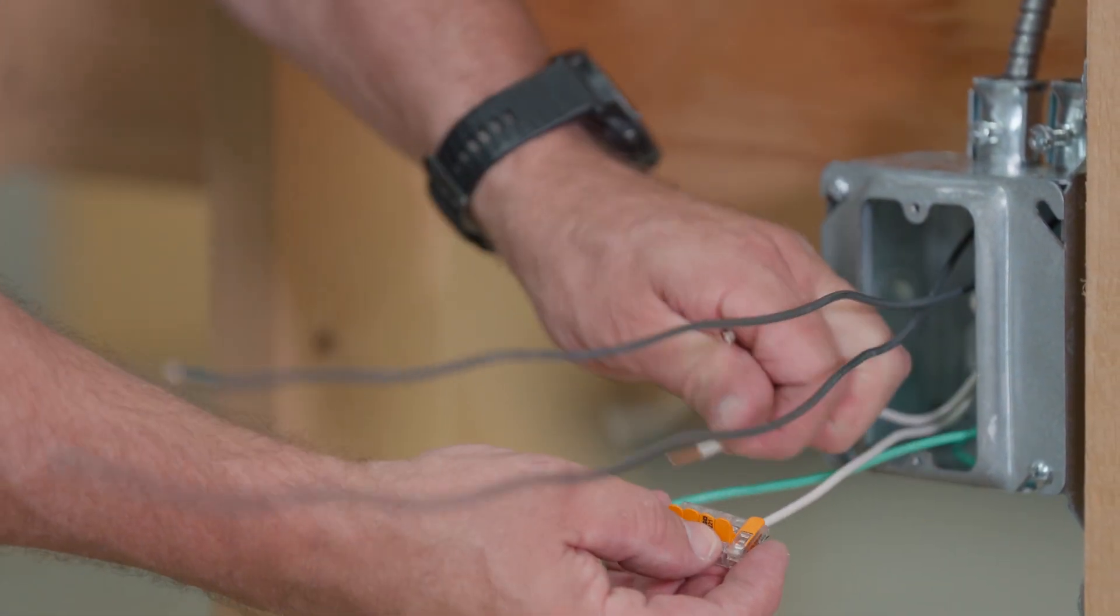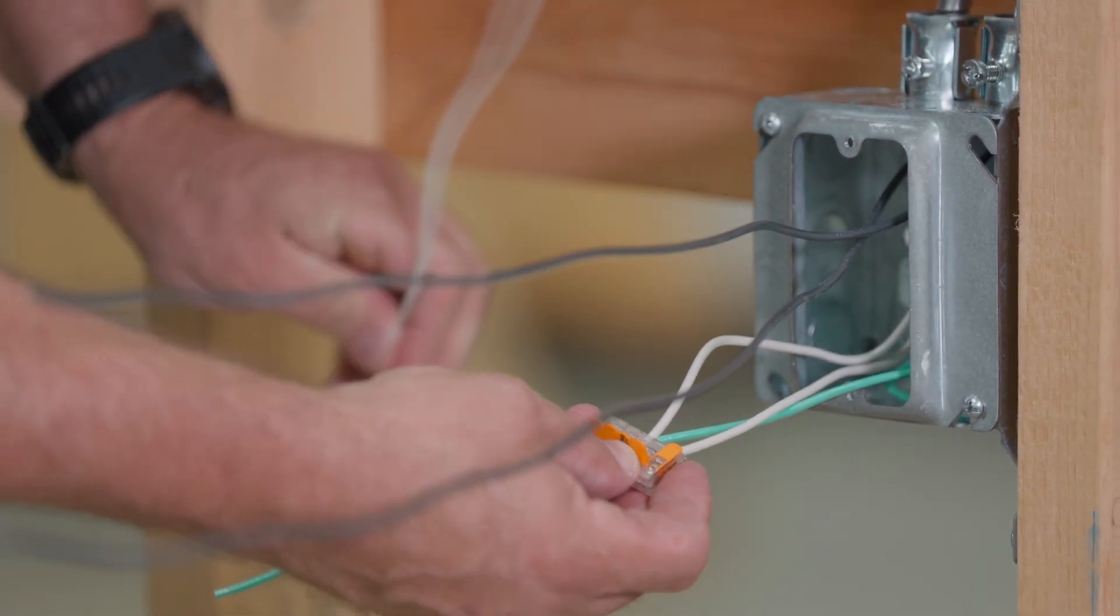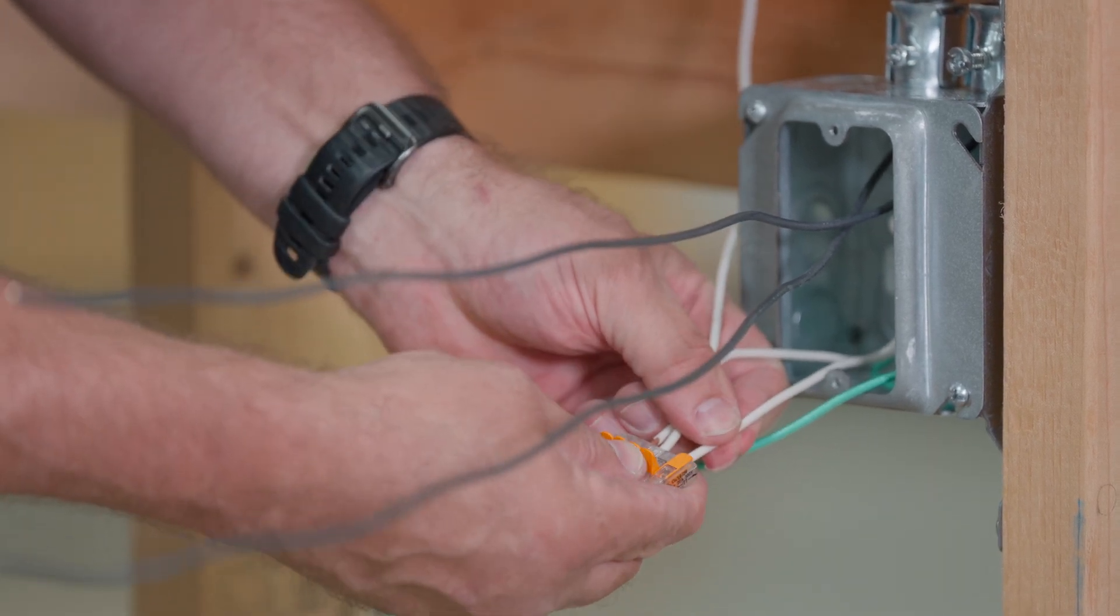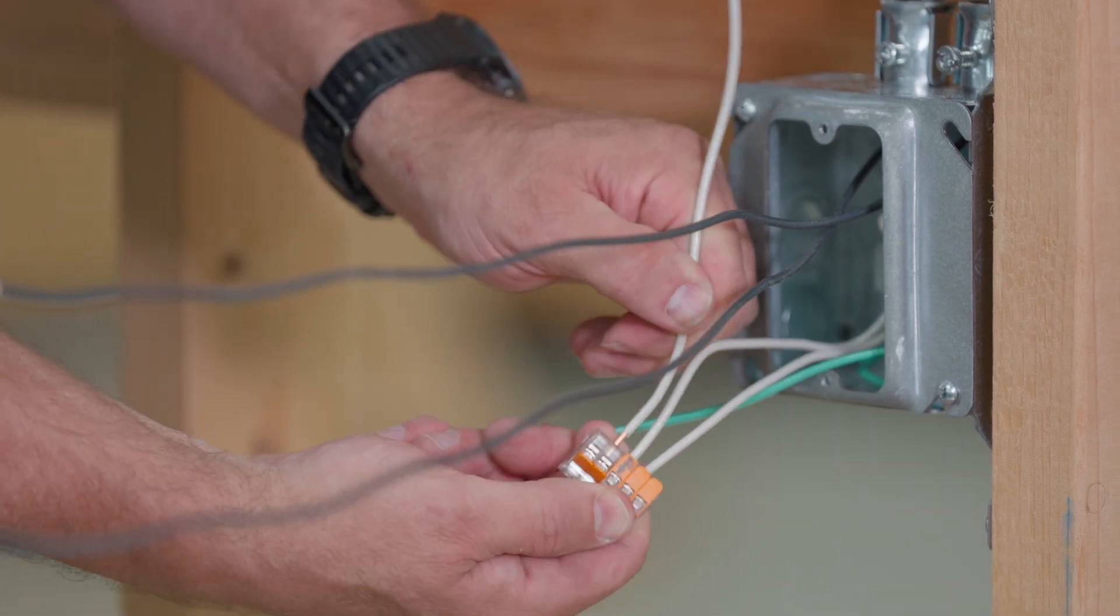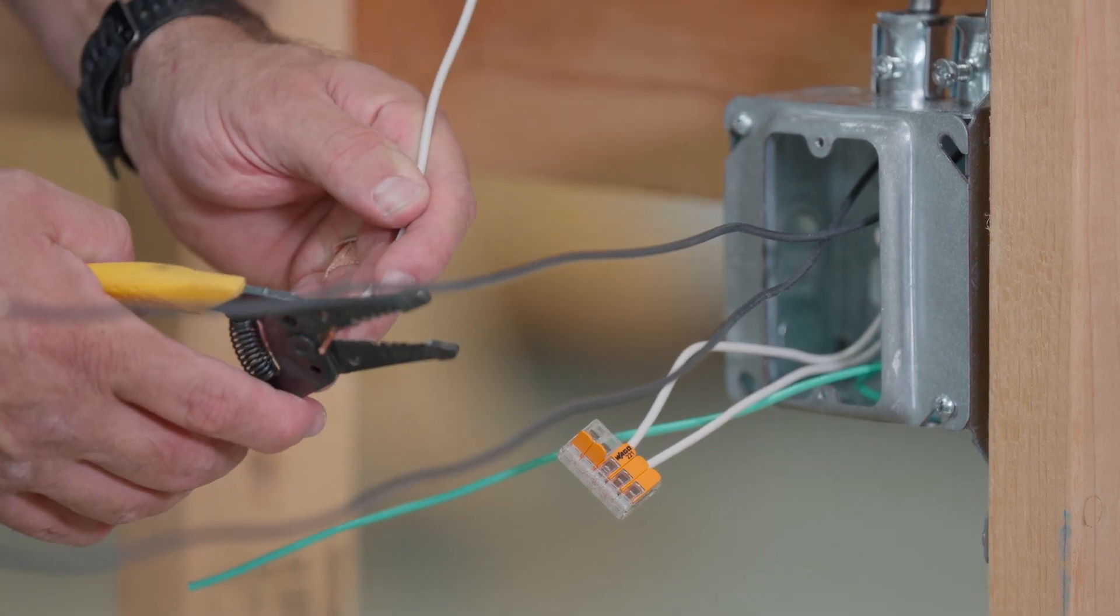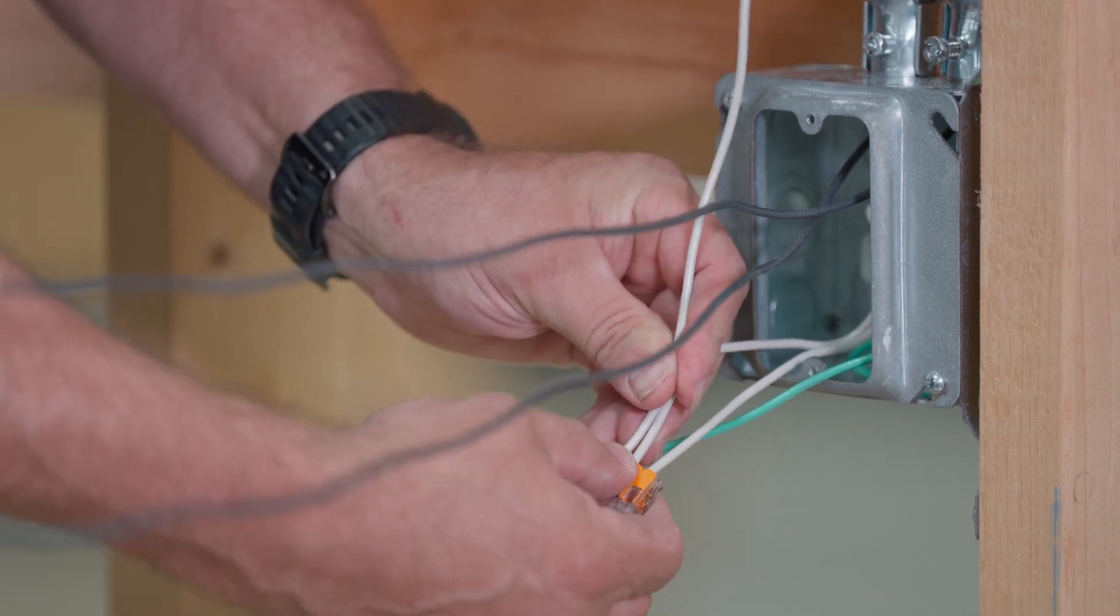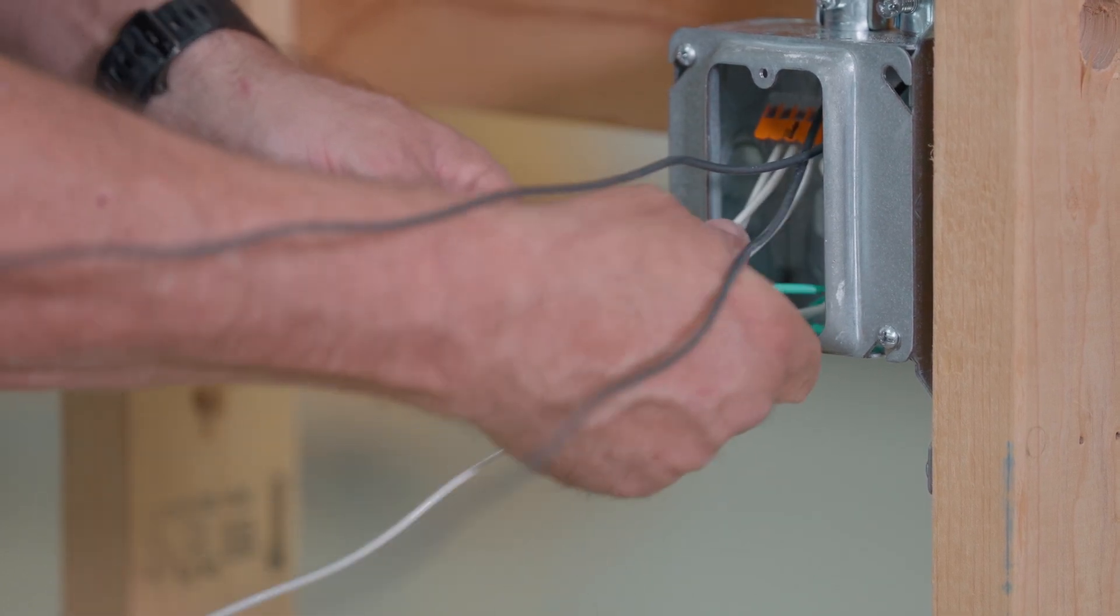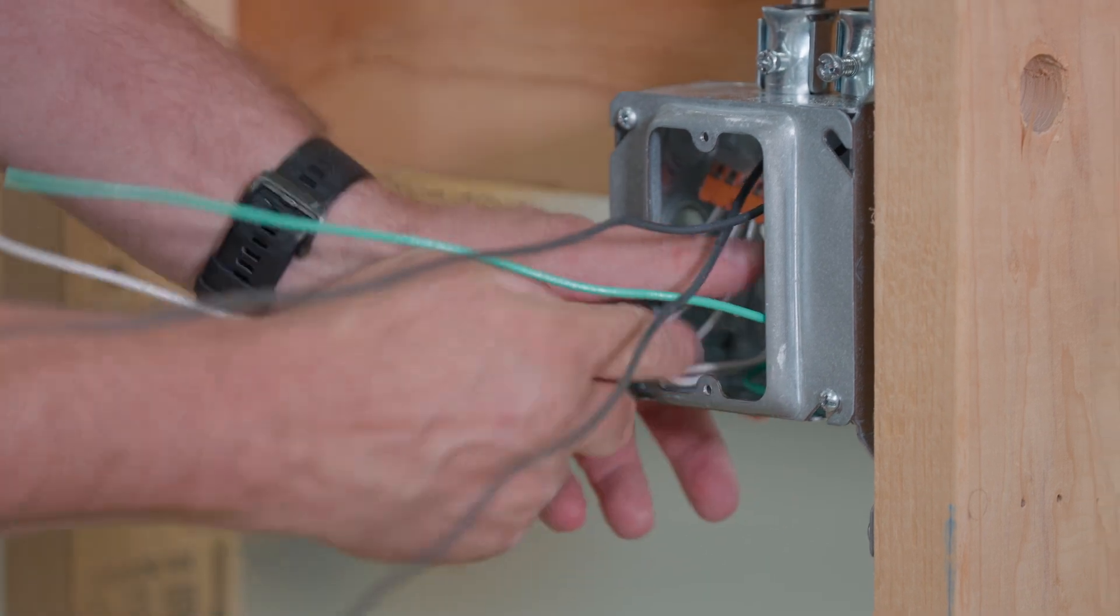And then we're going to get another push-in connector here. We're going to push this. Make sure all these wires go all the way in. Make sure that when you put it in there, you don't take too much strip off the wire. There's too much wire here. That was stripped too long. You don't want any wire showing when it's inside this. We want it to all be inside. Now they're all nice and tight. So we'll fold this also to the back of the box. Let's put it all the way to the back.